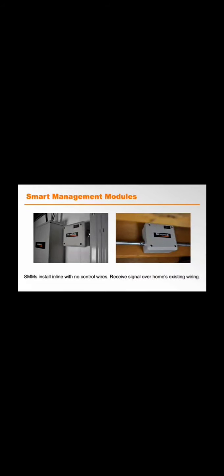Nobody believes me when I say how easy SMMs are to install, so I want to give a couple examples right here. Basically, they install in line with the home's existing wiring. They can go next to the panel if you have room, or they can just install, as you see here on the right, to existing conduit or to existing home circuits in some other part of the home, either near the panel or far away. They're incredibly flexible because SMMs don't require a control wire of any kind. They receive all their signals from the inverter over the home's existing wiring. So installation is really very simple.